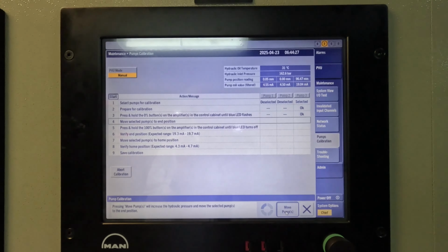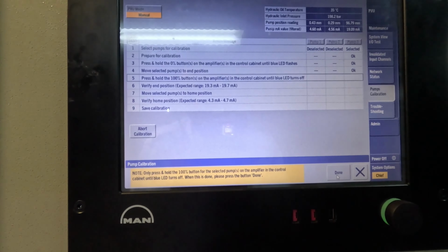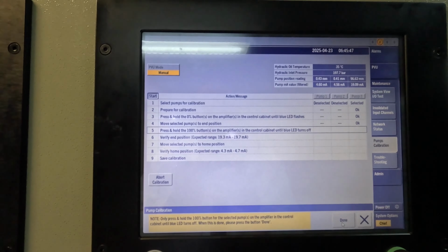Okay, Rohit, you can press and hold the 100% button on the amplifier till the LED turns off. So now the cargo engineer has to press the 100% button on the amplifier, as mentioned here, till the blue LED turns off. Once that is done, I have to press this next step. LED off. Okay, blue LED off. Thank you. Moving to the next step. Again you will see the pressure dropping, and we should get the current readings here. Now it says we need to verify the end position. Expected is 19.3 to 19.7 milliamps. The 0 position, that's the home position, is about 4.3 to 4.7. Let's do this by pressing done.